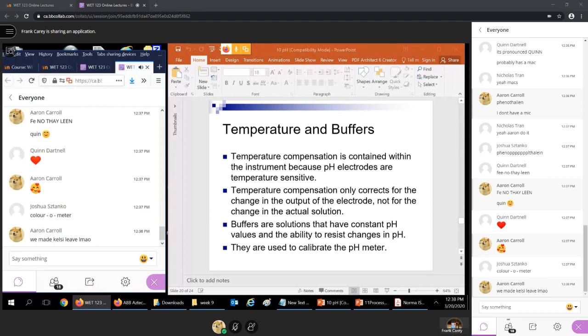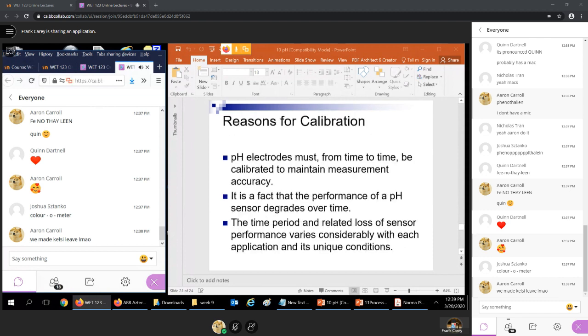Temperature and buffers. Obviously, temperature does matter with pH. So buffers and solutions must be temperature compensated, right? So when calibrating pH instruments. So most pH instruments do have a temperature sensor inside, and they will automatically compensate for the temperature. So we don't have to look up tables and stuff like that.